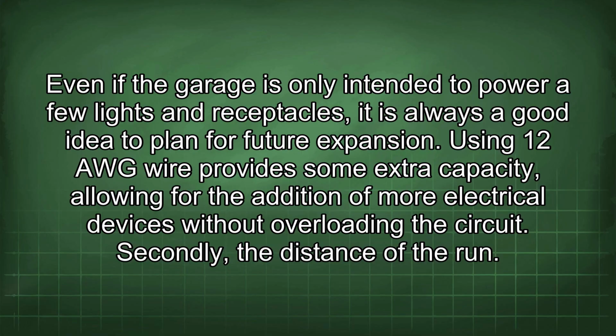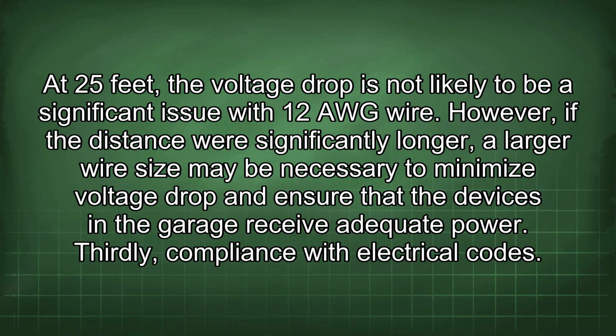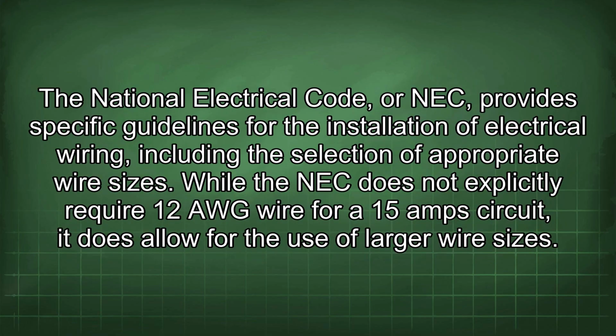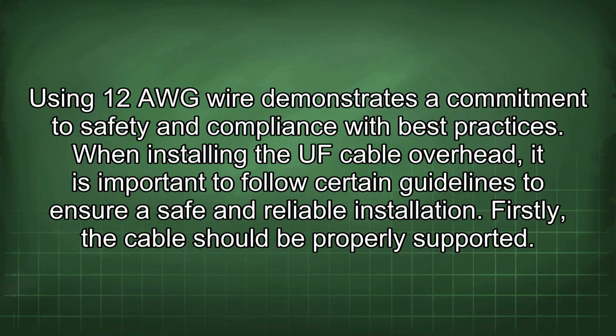Secondly, the distance of the run. At 25 feet, the voltage drop is not likely to be a significant issue with 12 AWG wire. However, if the distance was significantly longer, a larger wire size may be necessary to minimize voltage drop and ensure that the devices in the garage receive adequate power. Thirdly, compliance with electrical codes. The National Electrical Code, or NEC, provides specific guidelines for the installation of electrical wiring, including the selection of appropriate wire sizes. While the NEC does not explicitly require 12 AWG wire for a 15-amp circuit, it does allow for the use of larger wire sizes. Using 12 AWG wire demonstrates a commitment to safety and compliance with best practices.